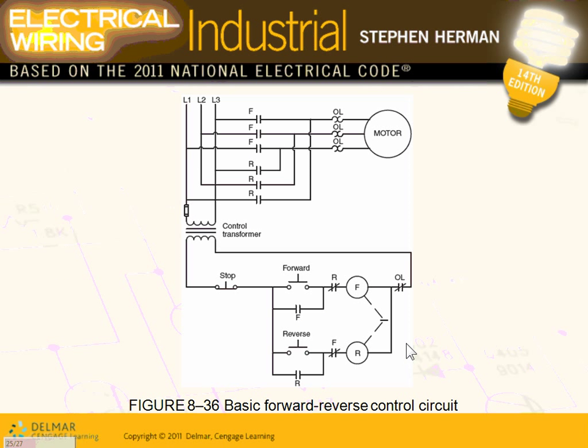Forward-reverse: this is another step — you can have forward-reverse with two sets of contacts driven by two magnetic starters. If I want to forward this motor, I close the forward contacts, which also opens the reverse circuit so I can't go reverse at the same time. When you close forward, the motor runs forward and the reverse is interlocked open. They call this mechanical interlocking and electrical interlocking.